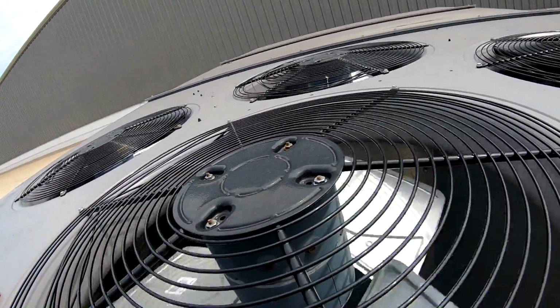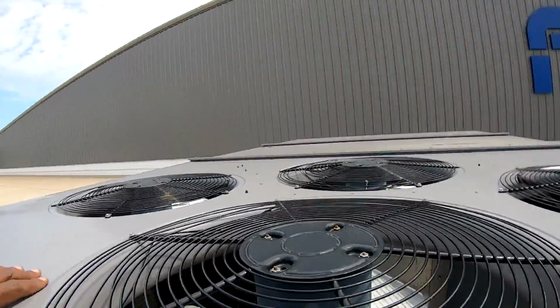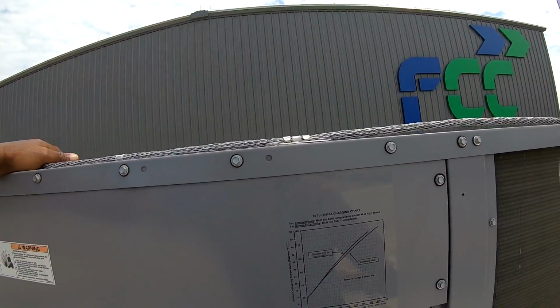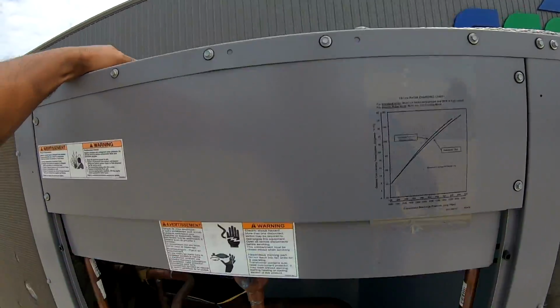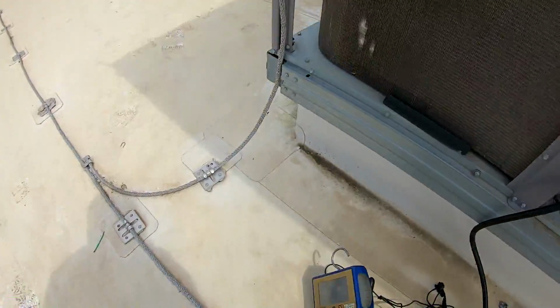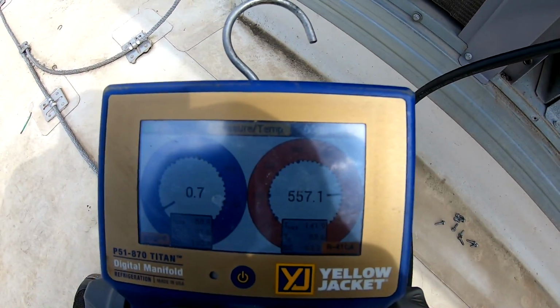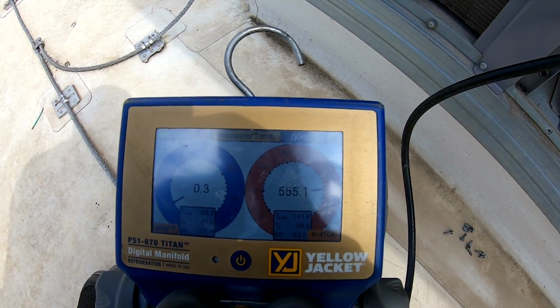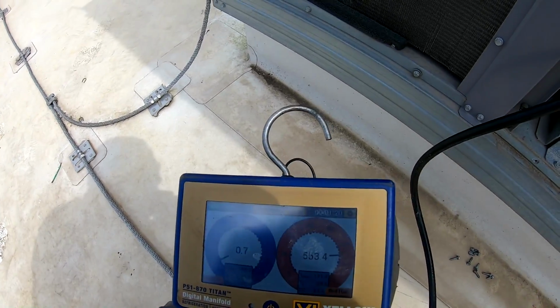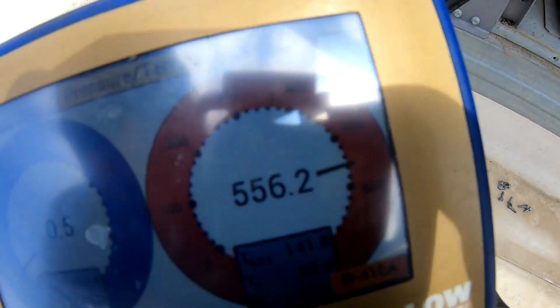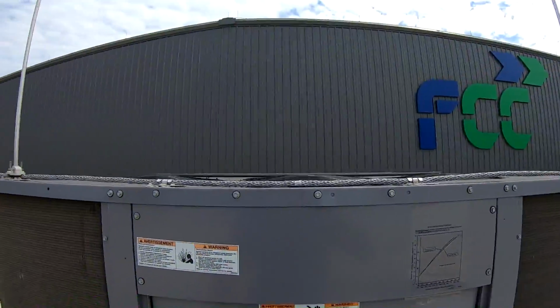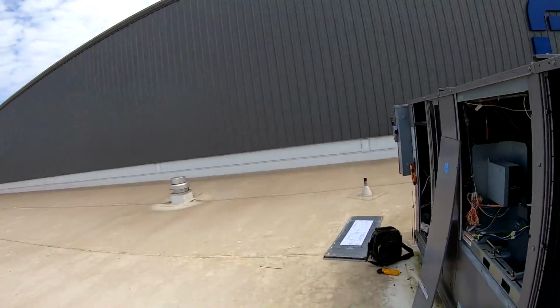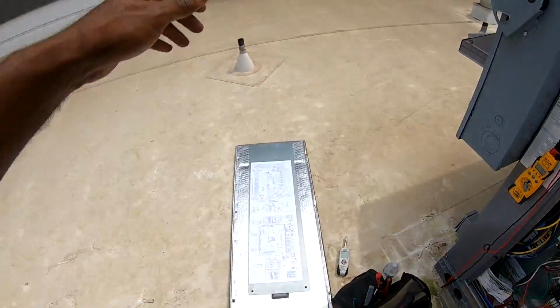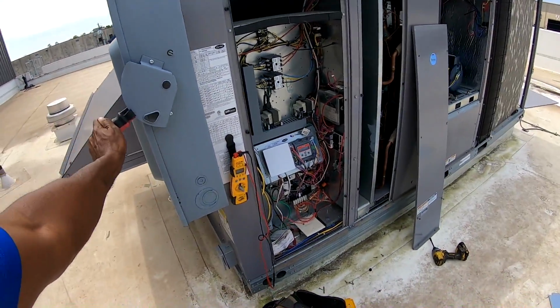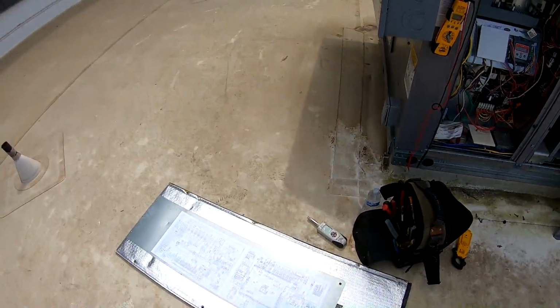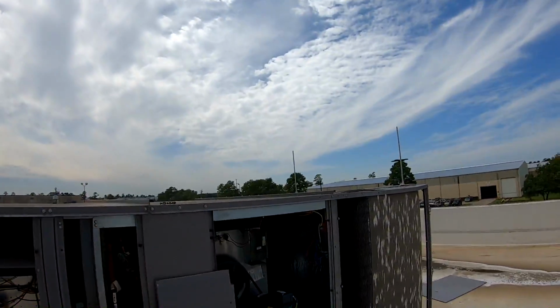It looks like ECM mode, but with that pressure being so high, I'm gonna look at the schematic and find out what's all hooked up to these fan motors. But with that pressure being so high, and it is kind of warm outside, it should be running. So I'm not very familiar with this Carrier, but I'll definitely figure it out. Like I say, my pressure is 550. I'm gonna go ahead and turn it off and track down what's running the fan motors. So, like I said, I know that's my problem. So I'm gonna read the schematic and find out what all is hooked up to this.